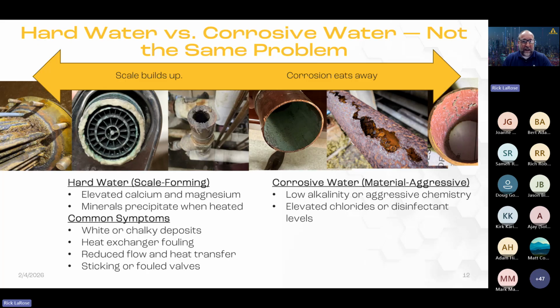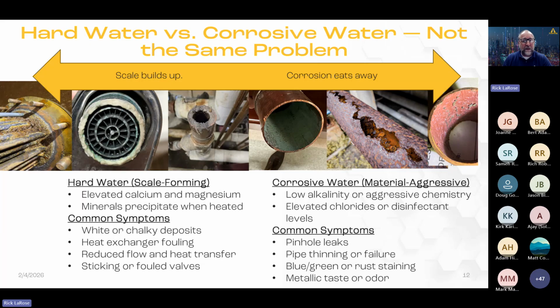Corrosive water, on the other hand, is material aggressive. This is often associated with low alkalinity, elevated chlorides, and aggressive disinfectants, especially if you're supplementally disinfecting your system. You get a little chlorine coming in from the street, but if you add additional chlorine, that can become very aggressive to your system. Those types of problems typically present as pinhole leaks, pipe thinning, staining, etching, and premature failures of that type.